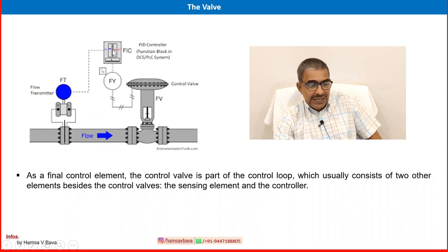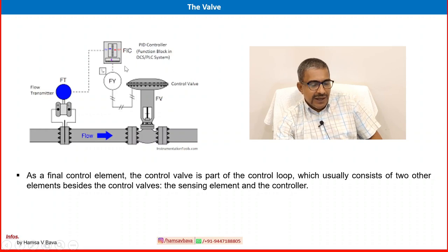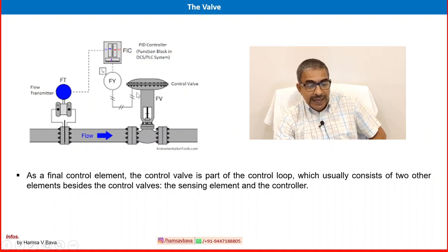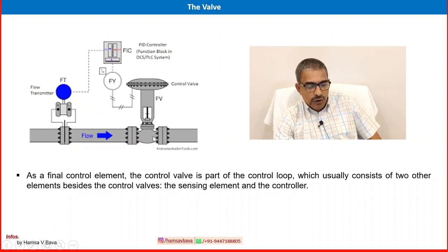The controller type shown here is a PID controller — proportional integral derivative — though we do not need to study that detail here. The controller output is electronic, and an I2P converter converts the electronic signal to a pneumatic signal, because most control valves operate on pneumatic signals — air is the driver of the control valve. Compressed air is provided through a positioner to the diaphragm or actuator, and the valve opens, closes, or throttles based on the instruction from the controller.